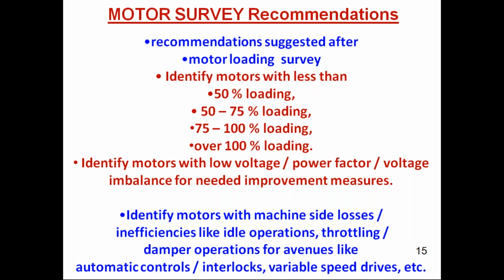If the motor is at 50 to 70% loading, it is ideal. At 75 to 100%, a motor can go to overload, because motors also get derated because of the tropicalized climate and the ambient conditions. We have to keep that in mind. Any motor above 100% loading, I don't say needs replacement straight away. We first look at what can be done to reduce the load, and if that is not possible, then we have to replace it.